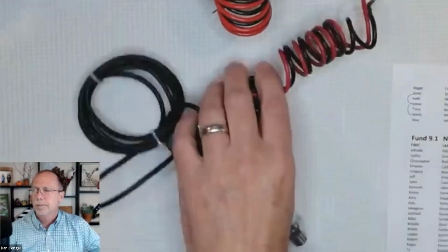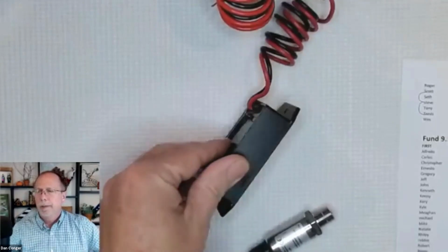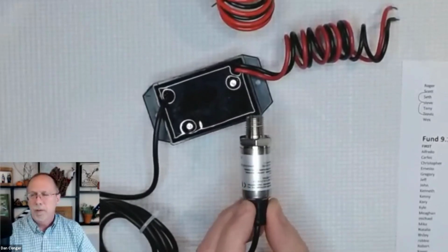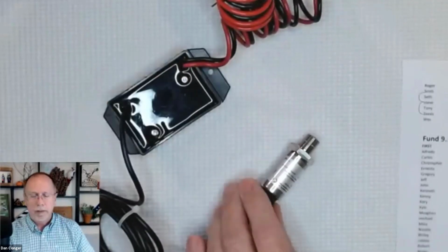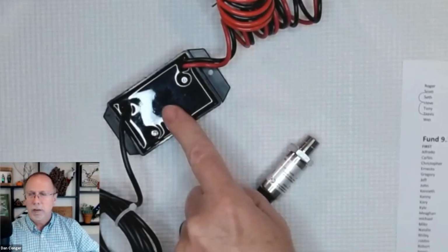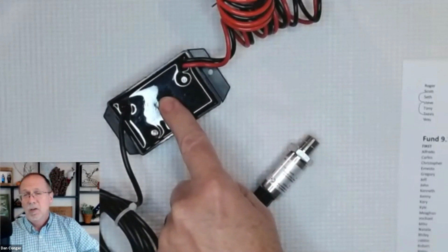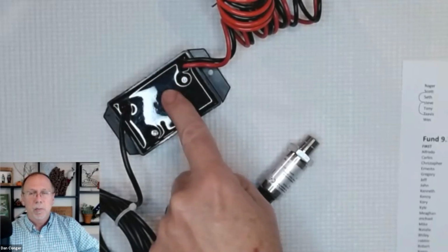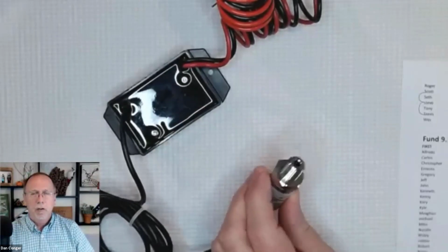Excellent question. Dave asked, would the sensor be installed in the bottom of the tank facing up? It doesn't matter. Let me switch my camera. So here's the biCoder. This just allows us to connect into the 2-wire system. Pressure transducers have been around for a long time. There's nothing particularly magic about it. What was magic was making this read 4 to 20 milliamps. That's analog, so how do we turn that into a digital signal? That's what this is all about. Honestly, 4 to 20 milliamp is used in a lot of different devices, and I'm nerding out trying to figure out what else you can run with this biCoder that reads 4 to 20 milliamps.